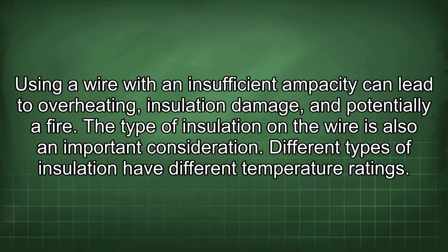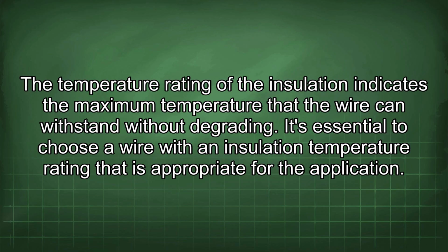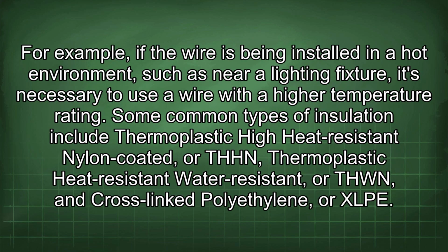The type of insulation on the wire is also an important consideration. Different types of insulation have different temperature ratings. The temperature rating of the insulation indicates the maximum temperature that the wire can withstand without degrading. It's essential to choose a wire with an insulation temperature rating that is appropriate for the application. For example, if the wire is being installed in a hot environment, such as near a lighting fixture, it's necessary to use a wire with a higher temperature rating.